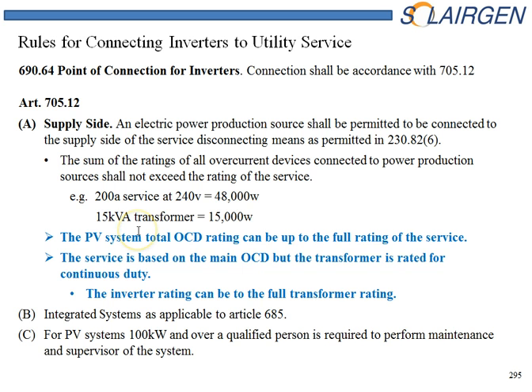When we look at the real capacity of the utility, we're looking at the transformer. That's the second thing we look at, but it will be the real limiter for us. Often with residential systems, we have either a 25 kVA shared transformer for two homes, or a single transformer for a single home at 15 kVA. Either one's going to limit us quite a bit, so our inverter capacity cannot be more than 100% of this rating. So those are the two things we look at: first, the maximum overcurrent device cannot exceed the service capacity; and second, our inverter rating cannot exceed the transformer rating.